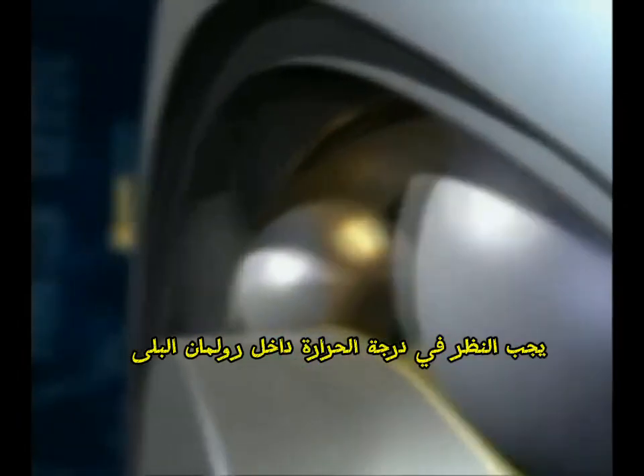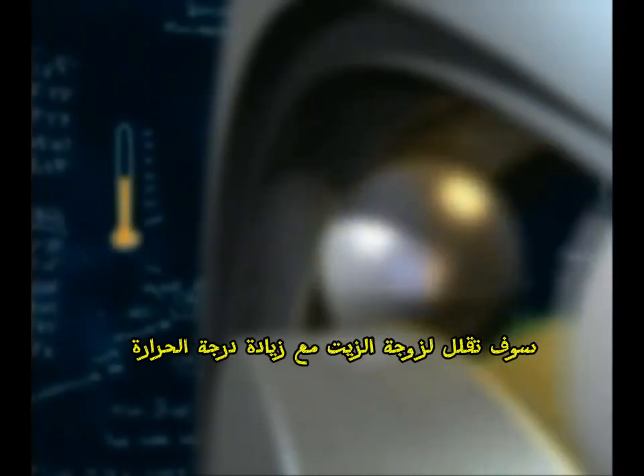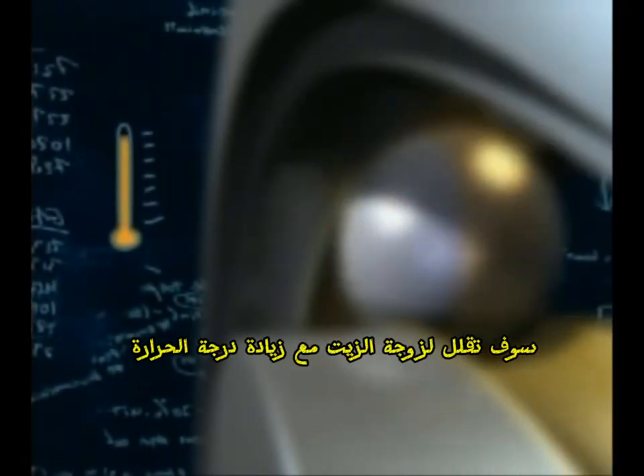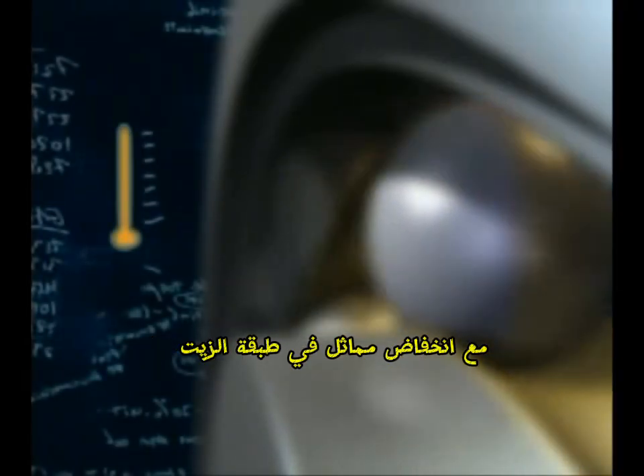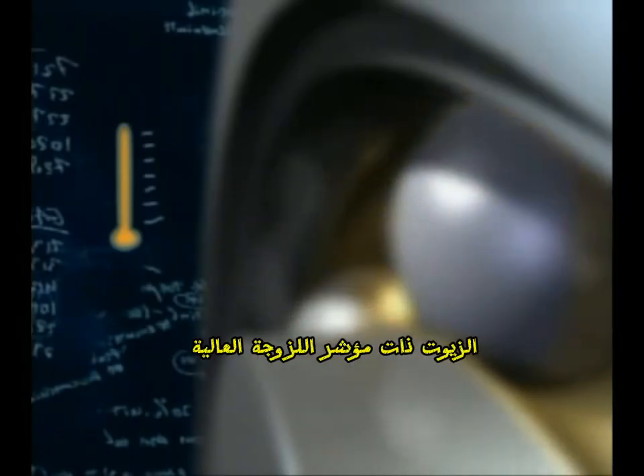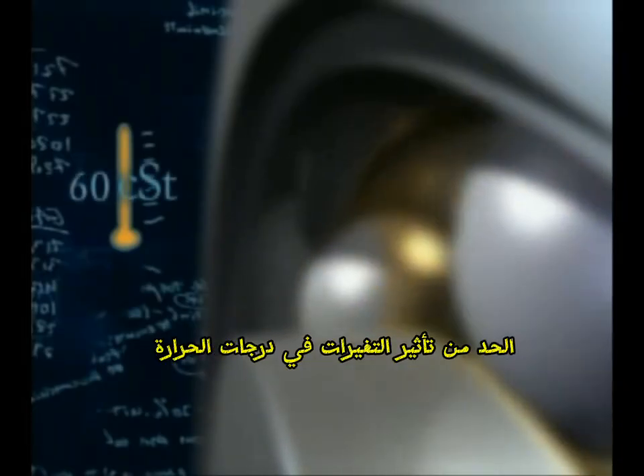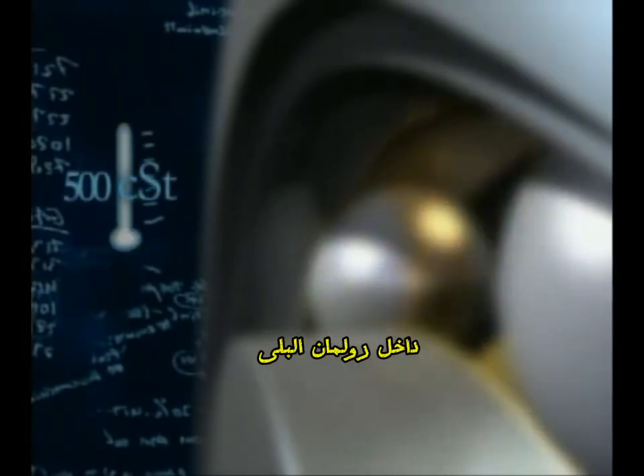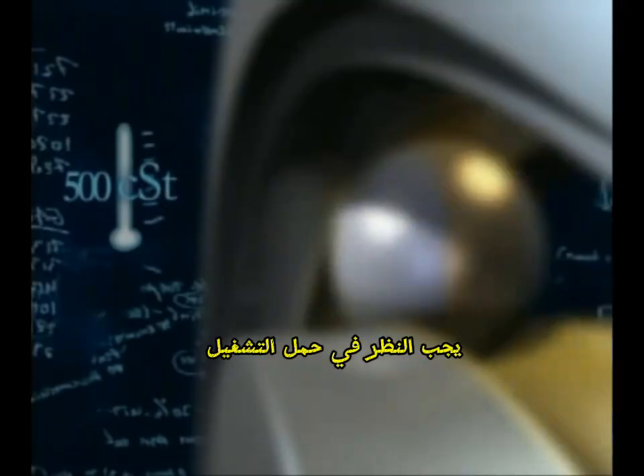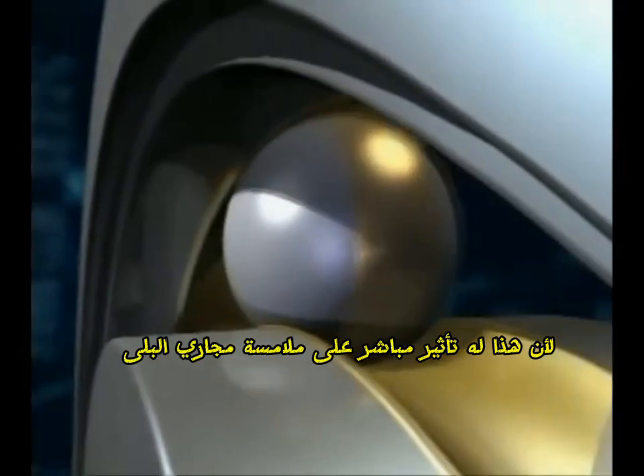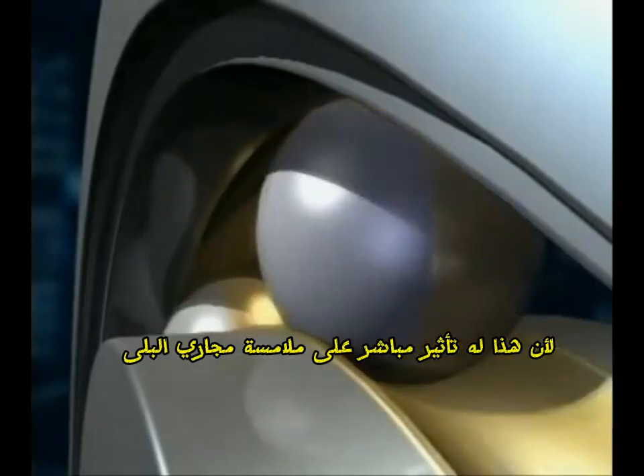Temperature within the bearing must be considered. The oil viscosity will reduce with increase in temperature, with a corresponding reduction in oil film. Oils with a high viscosity index limit the effect of temperature changes within the bearing. The operating load has to be considered, as this has a direct effect on the contact of raceways and all rolling elements.